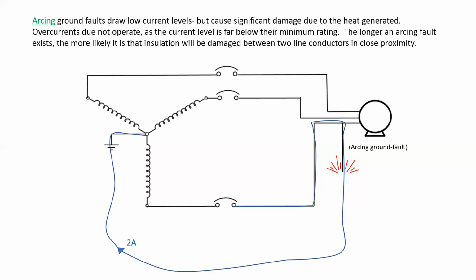And if that were to take place, the longer an arcing fault exists, the more likely it is that insulation will be damaged between two line conductors in close proximity. This leads to a full line-to-line short circuit, and of course, significant damage. And at this point, yes, the overcurrents would both trip.